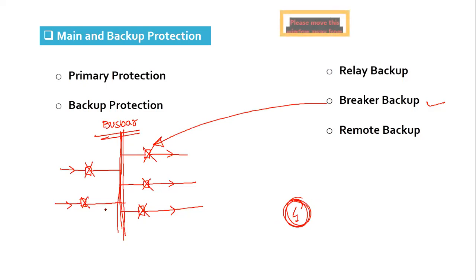Clear? Suppose there is a fault here on the line, and if this relay does not trip, then what do we do? We trip all the breakers associated with this substation. That is what breaker backup is.